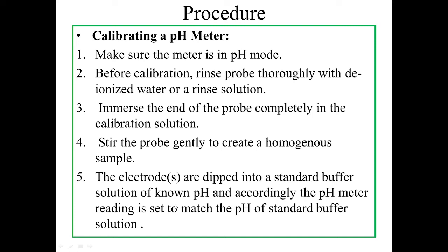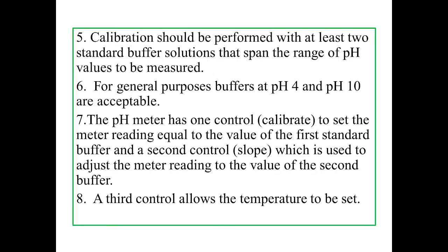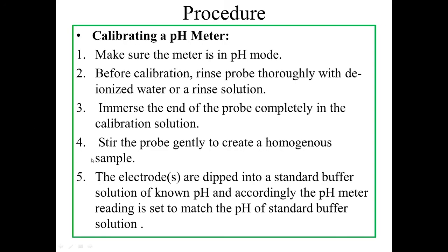For calibration purposes, we generally prefer using two standard buffers of two different pH. What are those? One may be acidic, that is pH 4, and another may be 9.6 or pH 10. So we select two standard buffer solutions. Dip the electrode in the standard buffer of known pH. Once you dip it in the standard buffer, you know the pH of the buffer.